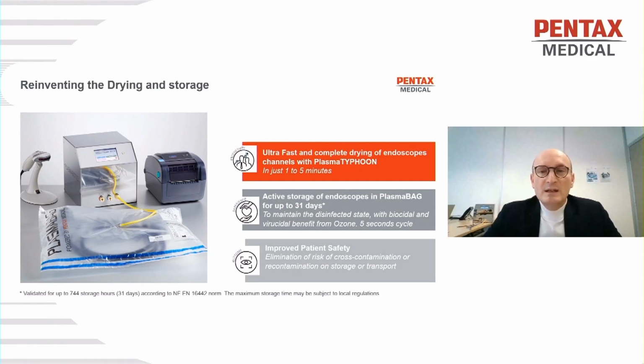After the drying, we can also perform an active storage of the endoscope inside the plasma bag, which allows us to keep the disinfection state of the endoscope for up to 31 days. I have to mention also that the maximum storage time may be subject to local regulation. So with these options, drying and storage, we can improve patient safety by eliminating the risk of cross-contamination or contamination during storage and transport.